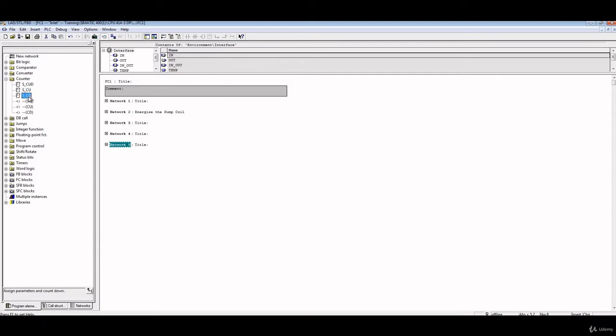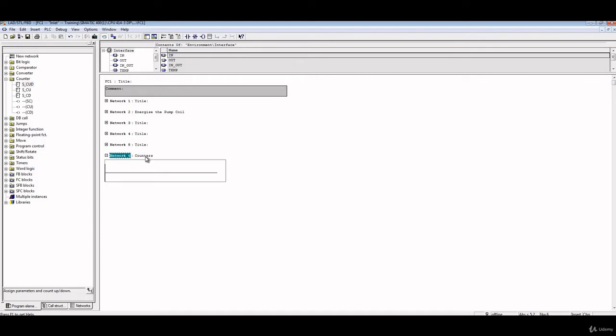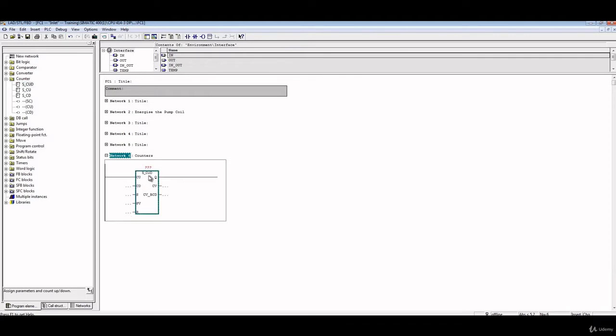So to understand more about the counter, we'll just create a new network. This network we will name it as counters. And then we'll put the first element, which is S_CUD, counter up and down. So counter up and down is used for counting up or counting down in the same element. First, it asks you to assign a name, a tag name for the counter.